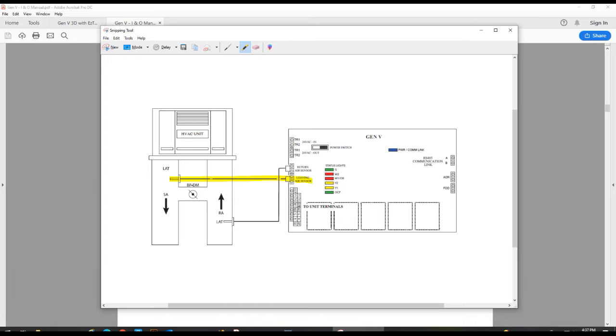If you need to extend the sensor out to get to that portion of the plenum, you can extend it out using 18 gauge thermostat wire and wire nuts or butt connectors. There's also a return air sensor that you want to install into the return air trunk, and make sure that is installed before your bypass as well.